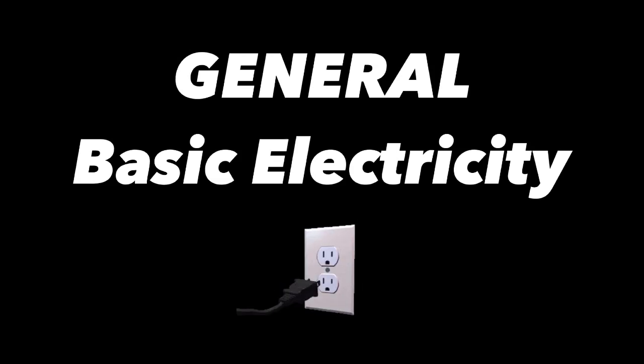What is the electrolyte used in a nickel cadmium battery? Potassium hydroxide and water. Why is a hydrometer not used to measure the state of charge of a nickel cadmium battery? The electrolyte of a nickel cadmium battery does not enter into the chemical changes that occur when the battery is charged or discharged.